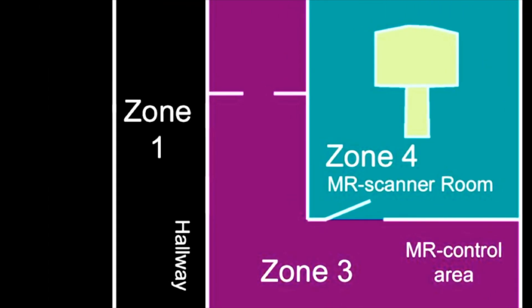Zone 1 includes all areas freely accessible to the general public. This is where the magnetic field poses no hazards, such as the entrance to the MR facility.